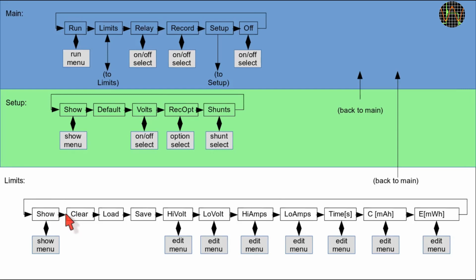Values and enabling or disabling are 2 separate functions, so you can have limit values defined numerically but choose not to enable them for the present run. I have done it this way because editing numbers with the up, down, left, right cursor keys is a bit slow, so you don't want to have to zero a carefully entered number just not to check for it at the current run, and it allows 0 as a valid limit value.